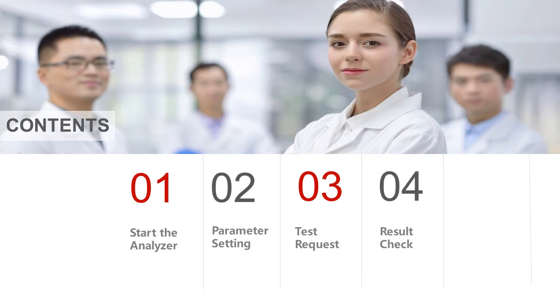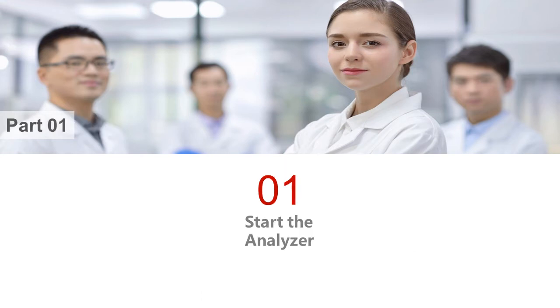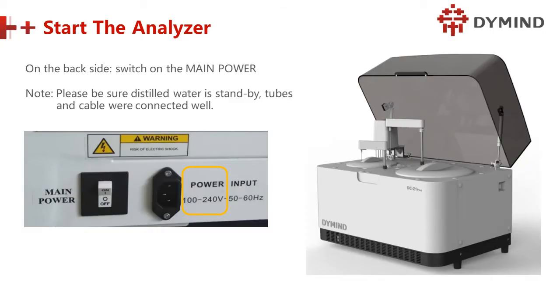So now we can start part one. Start the analyzer, and it's easy. We have two switches on our main unit. One is at the back, the main power key, right? If we are engineers, we should bring our tools. This tool is a multimeter, and we check the voltage, the ground voltage, and the stable frequency, and check that they are stable. Then we can turn on the machine, right? Otherwise, it's dangerous to switch it on. Yeah, and tubing and cables are connected, everything is connected okay.